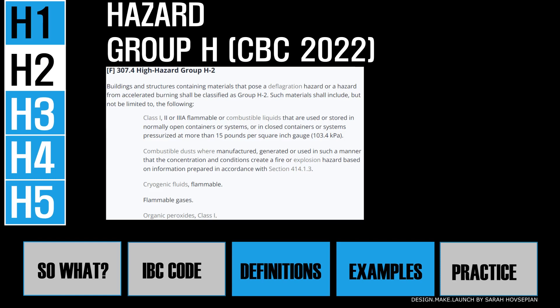H2 is a high hazard group as well — buildings and structures that contain materials that pose a deflagration hazard or a hazard from accelerated burning shall be classified as H2. This includes Class I, II or IIIA flammable or combustible liquids, and a whole list of other materials. Real-life examples would include isopropyl alcohol, ethanol, and diesel fuel. These liquids are classified by their flashpoint or their combustibility, and therefore would be an H2.